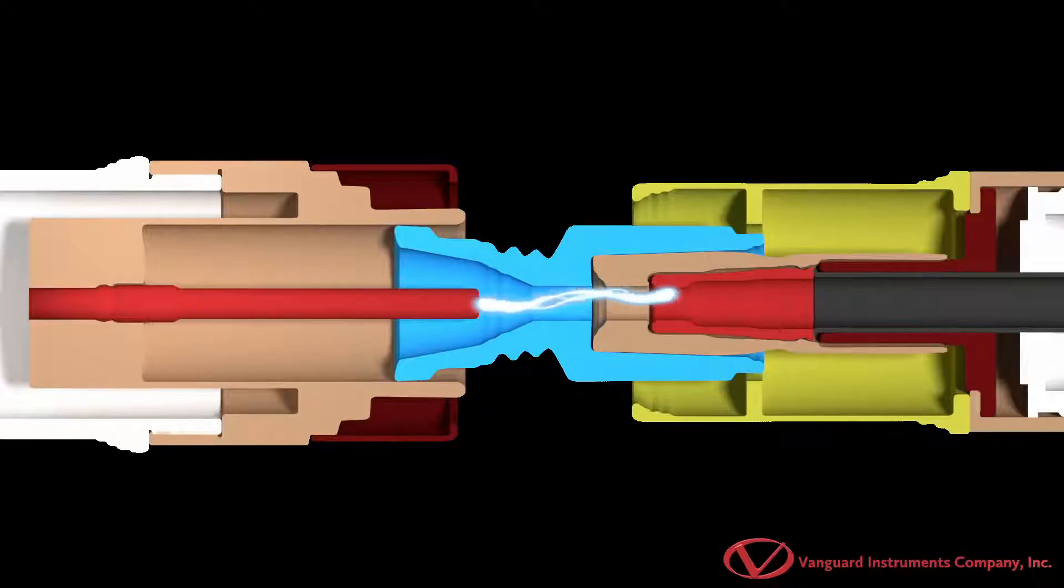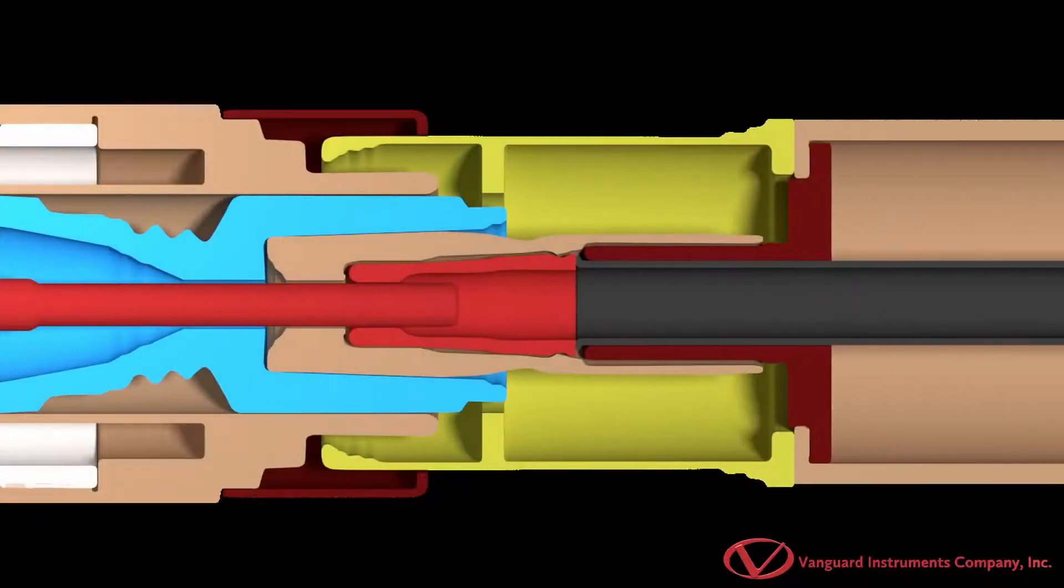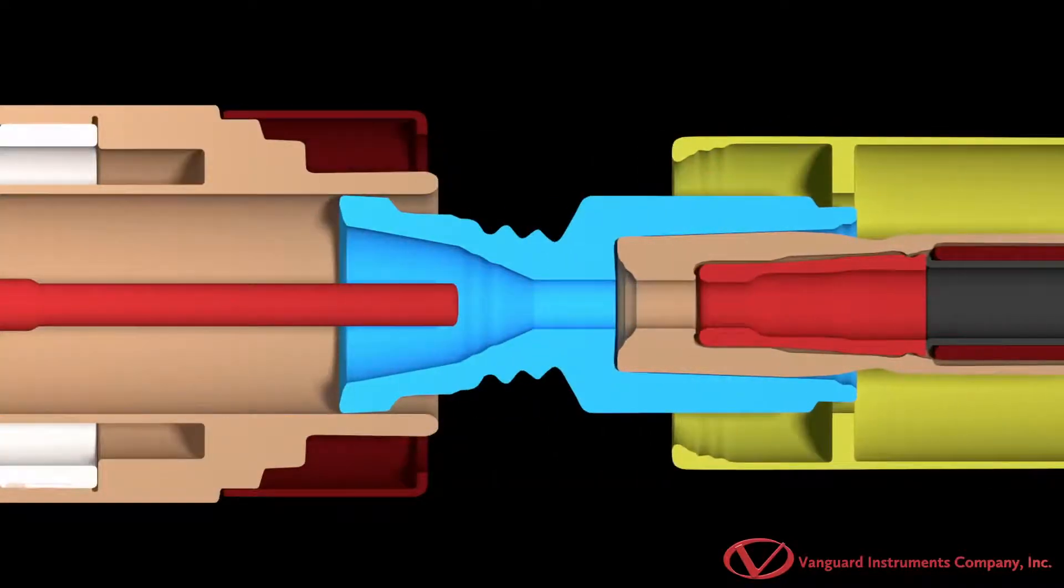In order to avoid arc re-ignition, the contacts must be separated with sufficient speed and the dielectric strength across the open contacts must be able to withstand the transient voltage.